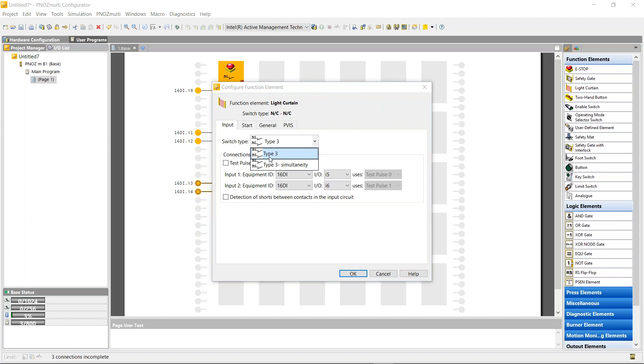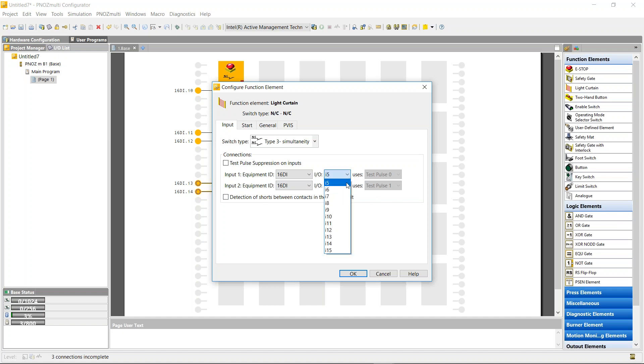I'm also just going to add in a light curtain. I have two types: type 3 normally closed and type 3 normally closed simultaneously. I'm going to use simultaneously. There's no need to use detection of shorts as the light curtain has its own OSSDS. I'm going to use I5 and I6.